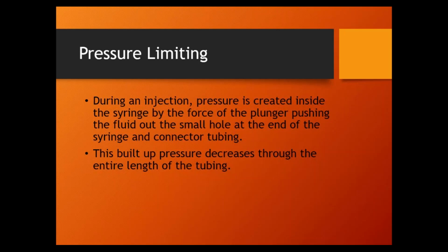No, actually what it does is it measures motor current feedback. During the actual injection, there's a circuit that's monitoring the current drop on the motor, and that's how it determines what pressure it's actually shooting. Now, some injectors do have pressure sensors in them, but I think they all still use the motor current feedback. Medrad uses both these days. They have a strain gauge. The strain gauge? And then they also do the motor current, so they're comparing the two. Okay. And then looking at the delta. Okay. Yep.